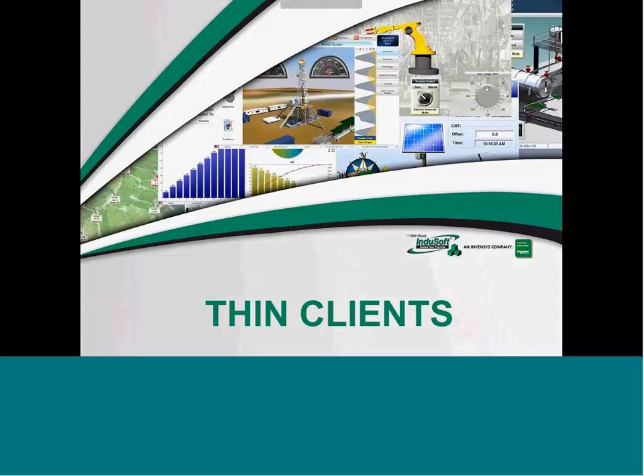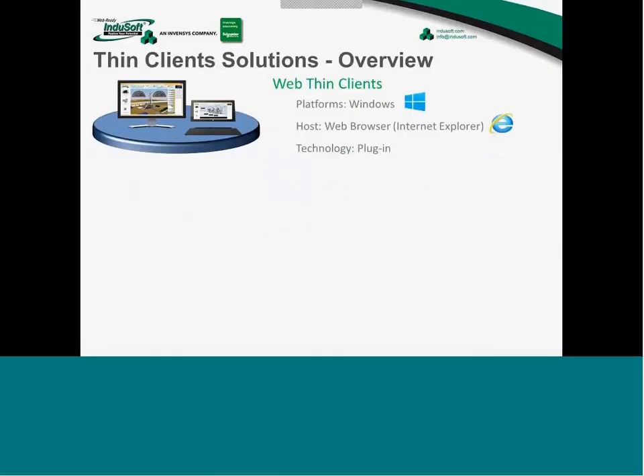And InduSoft supports different types of thin clients as well. A thin client is a remote station, not the runtime station necessarily, but a remote station, which has TCP access to the runtime station where you're running the software, where you're running Studio Manager. And from this remote station, you have access to the graphical interface, even though you do not have to install the product, the application, the configuration files, nor the license on the thin client stations. That's why we call them thin clients. So we support three types.